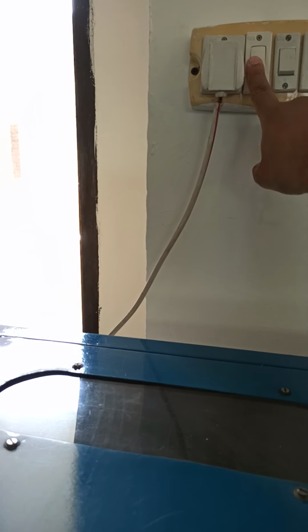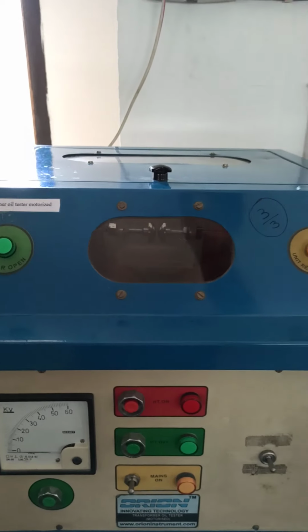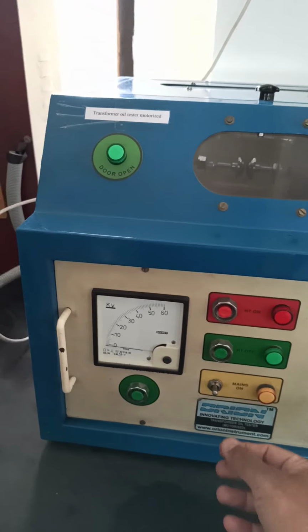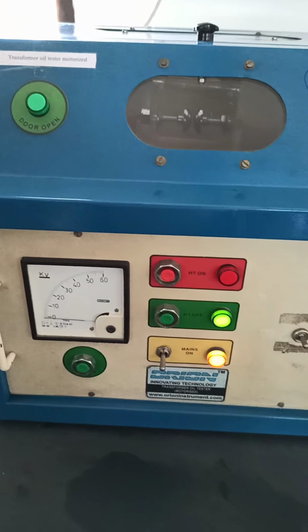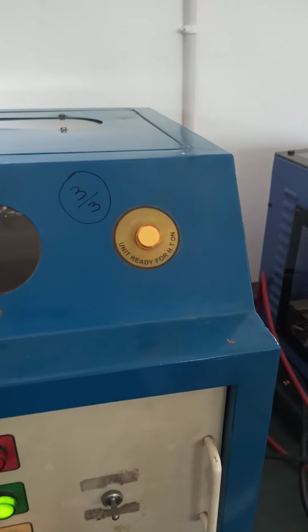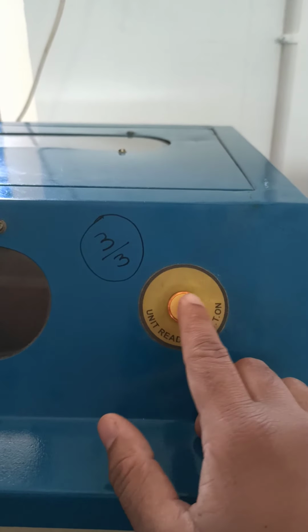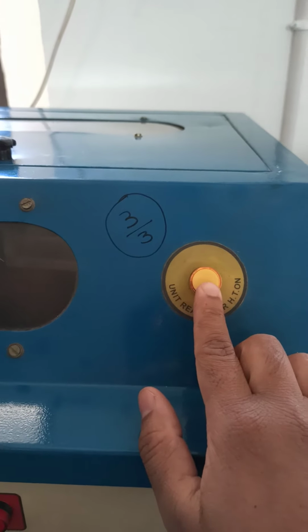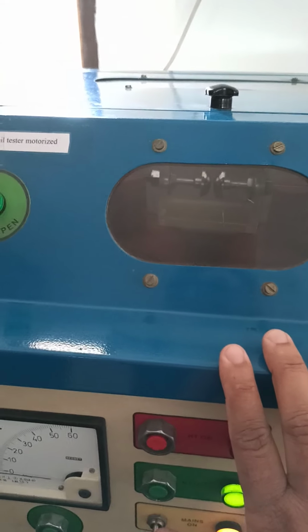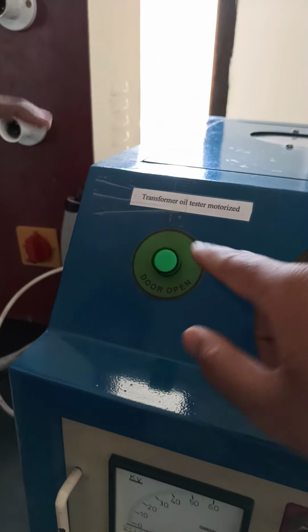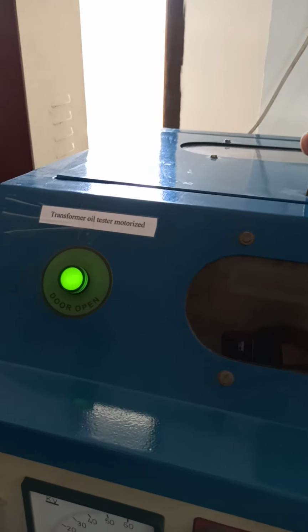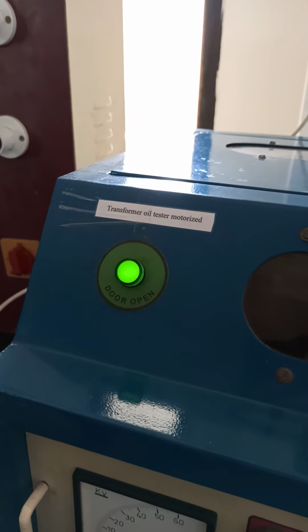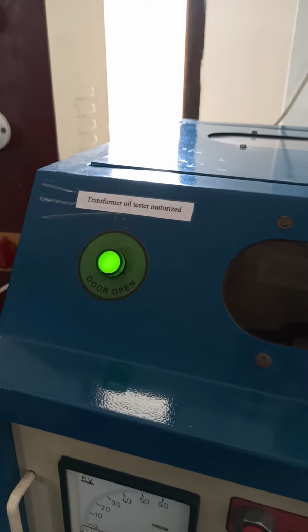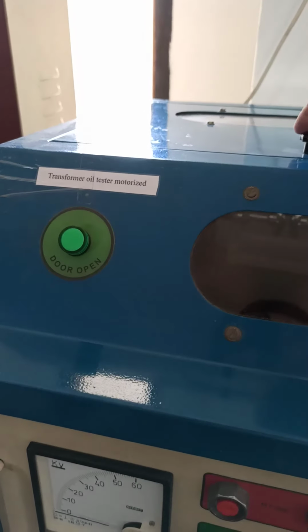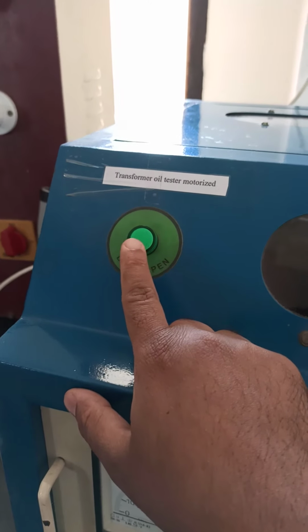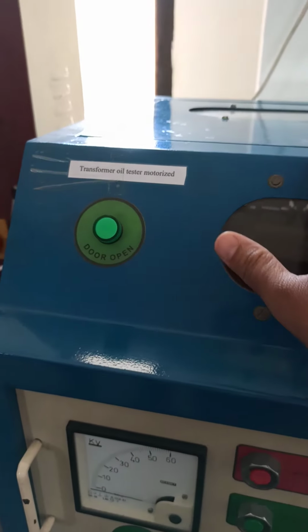So I will turn on this. Now you can see when I have turned it on, nothing is there. So what you need to do, you have to turn on this mains on. Now this mains is on, but you can see that the unit ready for HT on indicator is not glowing. So this unit is not ready for the test. Another thing is this door open. If I open this lid, now this indicator glows. It means this door has some problem, it is not properly closed. So you have to press it properly so that this LED should be in off position. So now it is okay, this door is properly closed.